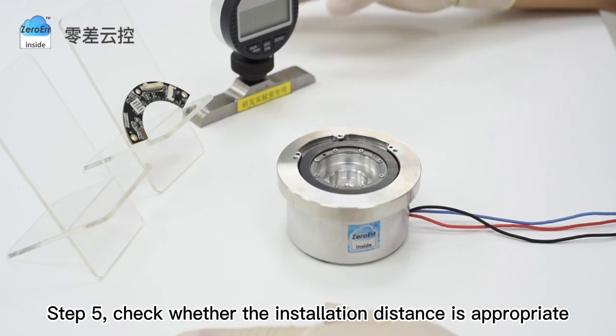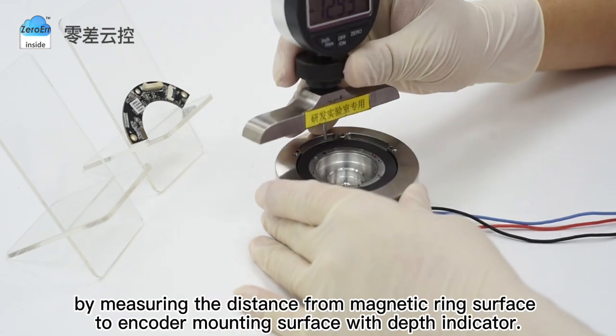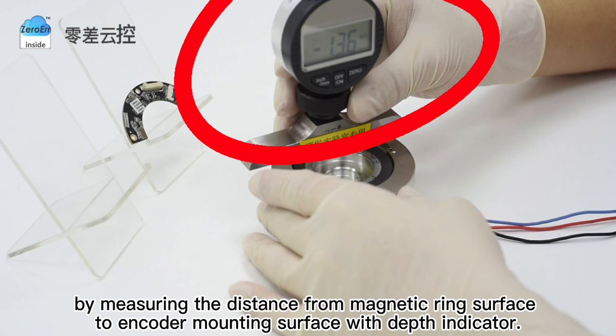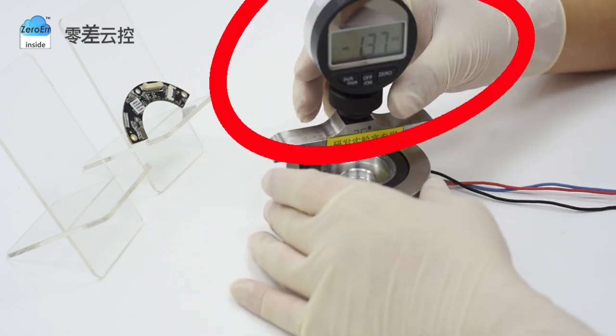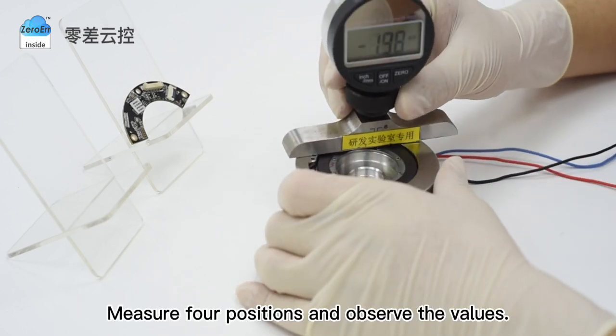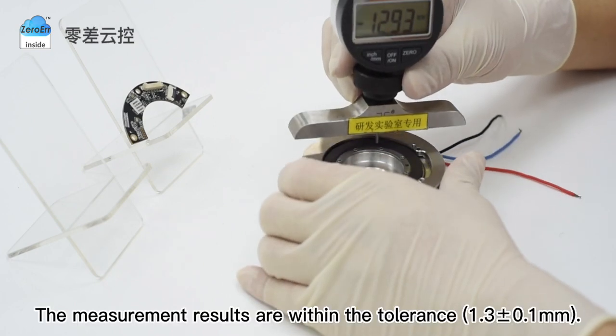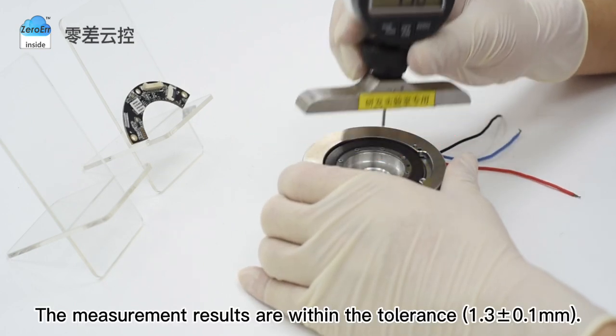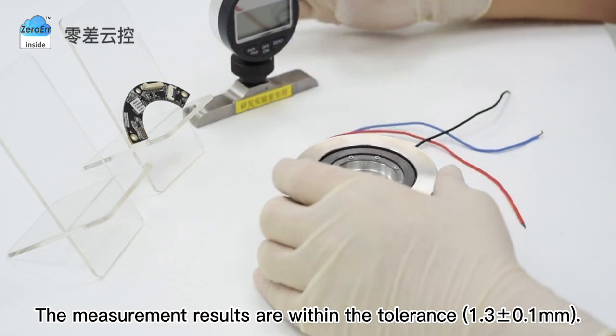Step 5, check whether the installation distance is appropriate by measuring the distance from magnetic ring surface to encoder mounting surface with depth indicator. Measure 4 positions and observe the values. The measurement results are within the tolerance, that is, 1.3 plus or minus 0.1 mm.